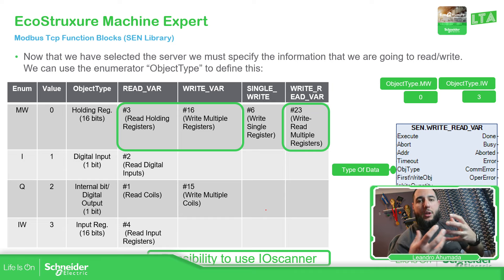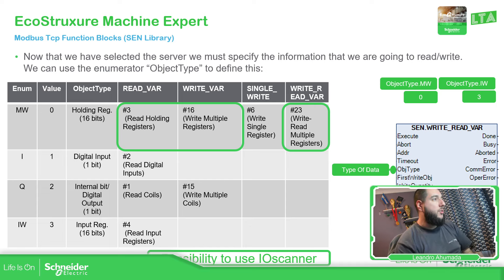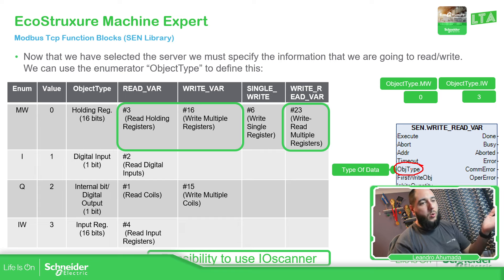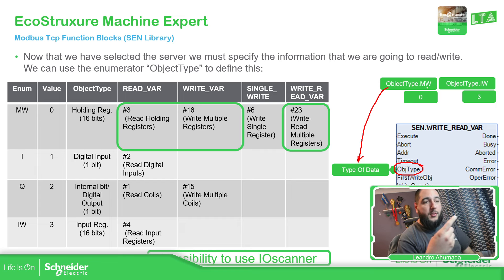Now we need to define how we're going to communicate to the server and how the data is going to be that we want to read and write. In each of the function blocks, there is a specific parameter that we need to configure, which is the object type. We can use an enumerator in order to easily assign the value, or we just use a constant. The options are MW, I, Q, and IW. Depending on this variable, it determines which Modbus function block you're going to use to communicate with the device.